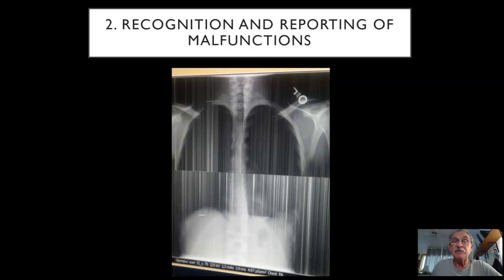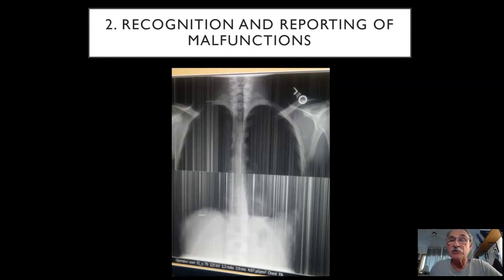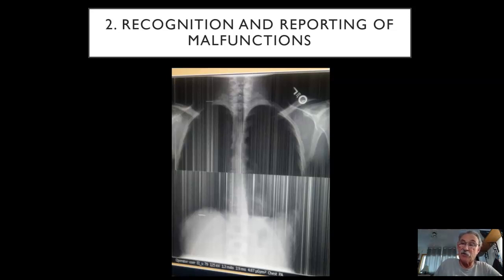If your X-ray image comes up looking abnormal, you might expect that we have a problem somewhere. This is not something that we as technologists can fix — this is a malfunction somewhere in the processing chain. For example, I can see the bony architecture of the shoulders and the marker clearly, but I'm not seeing the lung fields and there's a very strange artifact going through it. This is something we would need to communicate immediately to the clinical engineer, who could come and determine what the problem is and reset or repair it.